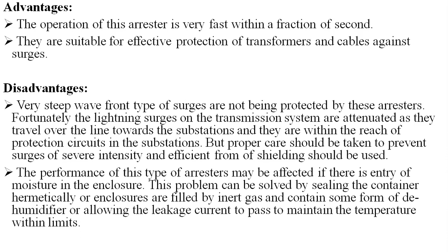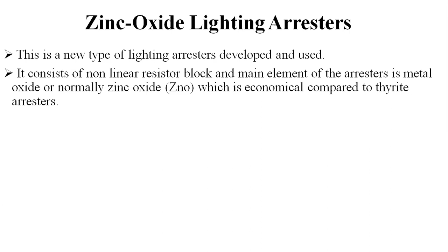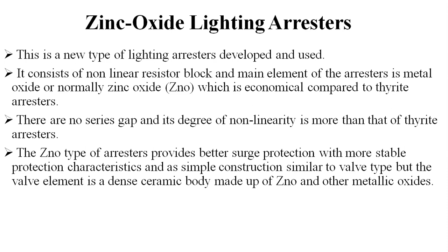Coming to zinc oxide lightning arrestors. This is a new type of lightning arrestor that has been developed and is used now, and it consists of a non-linear resistor block. The main element of the arrestor is a metal oxide, normally zinc oxide, which is economical compared to thyrite arrestors. There is no series gap, and its degree of nonlinearity is more than that of thyrite resistors. The zinc oxide type of arrestor provides better surge protection with more stable protection characteristics, and has a simple construction similar to the valve type, but the valve element is a dense ceramic body made up of zinc oxide and other metallic oxides.